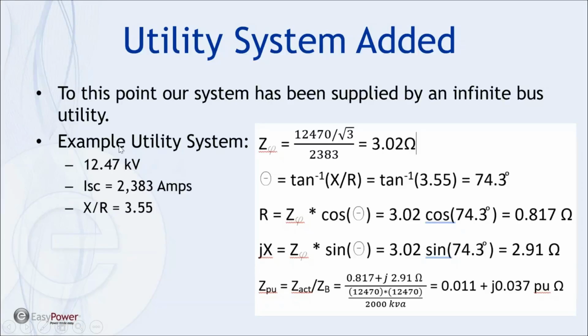Now, what we need to do is turn this information, this is what I do anyway, with EasyPower it's real nice, you just plug these numbers into the system. But if you want to know how these things work in the per unit world, we need to convert this. First of all, we need to convert it to an ohmic impedance. Because we have an X over R, it means we're going to have some R and some jX, and jX is going to be 3.55 times bigger than R. So we need to convert these items into ohms and then take those ohms and put them into the per unit system. Now, how's that done? Well, the short circuit current that is relayed here, you have to think of your system as basically a single phase representation.